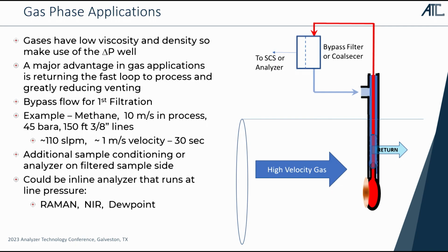So how do we apply this? What's good about it? In gas phase applications, they work really, really well. We have no issues with priming because gases are compressible. And so for gas phase applications, we can put this into any line that has a high velocity gas flow. It's going to drive flow up through the center region. We might use that to drive past a filter. But again, it could be driving through something like a flow cell for a Raman analyzer. Could be driving through the flow cell for a near infrared or an infrared analyzer. It could be a hydrocarbon dew point analyzer sitting there. We can use it to drive continuous flow.